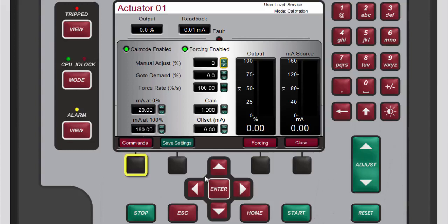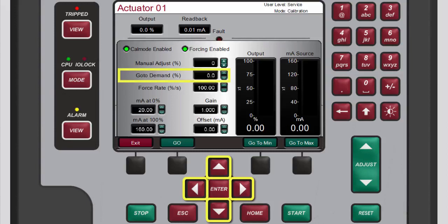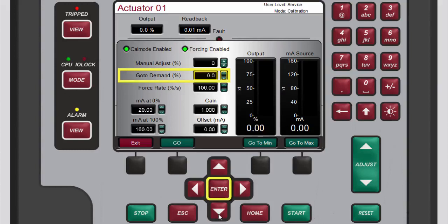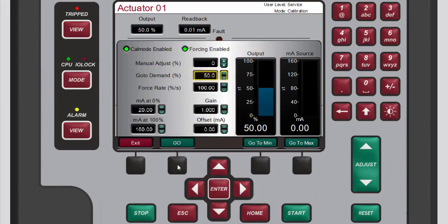To use go to values, press the black function key below commands. A new set of buttons — go, go to minimum, go to maximum — displays on the menu bar. Use the navigation cross keys to highlight the go to demand box. To change the current value in the go to demand box, either use the adjust keys, or press enter, use the numeric keypad to enter a new value, and press enter again to confirm. Now press the black function key below go — notice that the value in the output gauge updates automatically to match the go to demand value. The other two go to buttons can be used to drive the demand to the minimum and maximum values of 0 and 100 percent respectively.